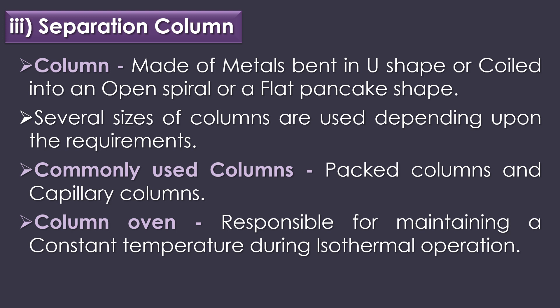The third part of gas chromatography is the separation column, which is the heart of the instrument. The column is made of metal bent in a U-shape or coiled into an open spiral or flat pancake shape. Several sizes of columns are used depending on requirements; the commonly used columns are packed columns and capillary columns. The column is enclosed by a column oven responsible for maintaining a constant temperature during isothermal operations.